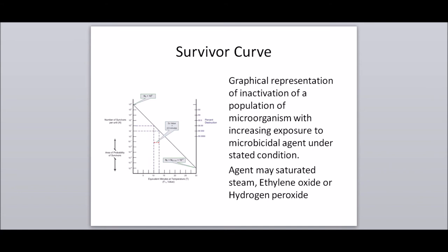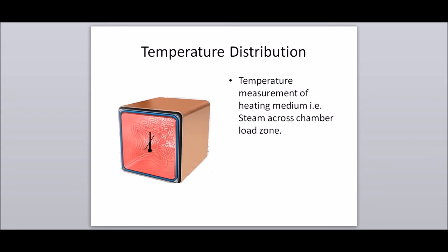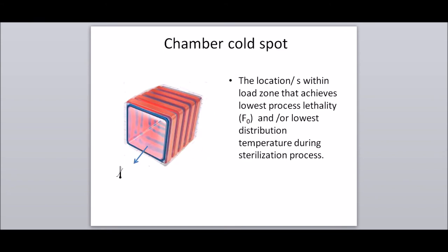The agent used may be saturated steam, ethylene oxide, or hydrogen peroxide. Temperature distribution: the measurement of the heating medium — i.e., steam — across a chamber load zone. Chamber cold spot: the location within the load zone that achieves the lowest process lethality, i.e., F0, and/or lowest distribution temperature during the sterilization process.